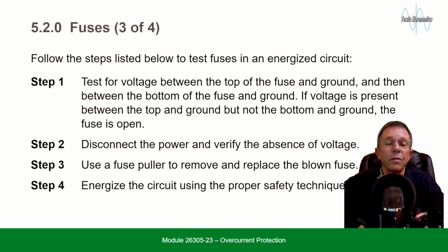Follow the steps listed below to test fuses in an energized circuit. Step 1. Test for voltage between the top of the fuse and ground, and then between the bottom of the fuse and ground. If voltage is present between the top and ground but not the bottom and ground, the fuse is open. Step 2. Disconnect the power and verify the absence of voltage. Step 3. Use a fuse puller to remove and replace the blown fuse. And Step 4. Energize the circuit using the proper safety techniques.